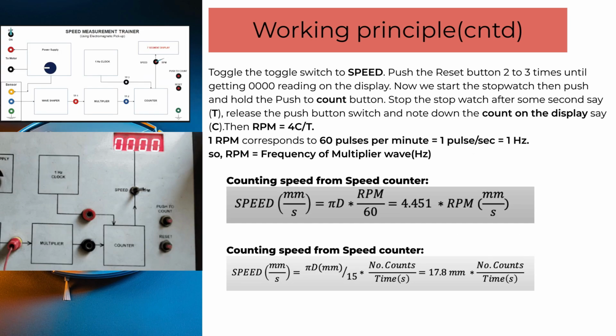Now we toggle the toggle switch to speed. Basically, we push the reset button 2 to 3 times until we get a 0 reading on the display. Now we start the stopwatch, then push and hold the push to count button. We then stop the stopwatch after some seconds, say after 5 seconds. Then we release the push button switch and note down the count on the display.